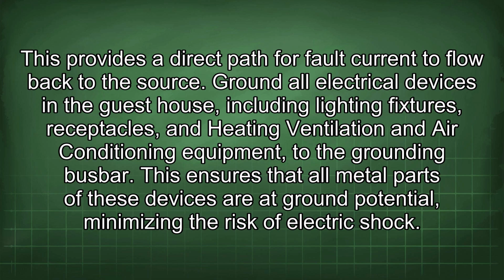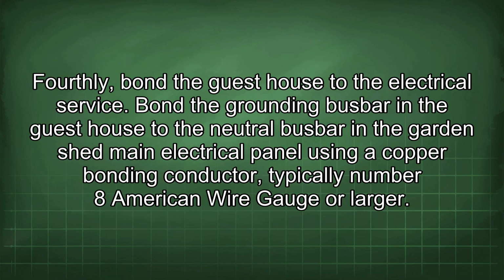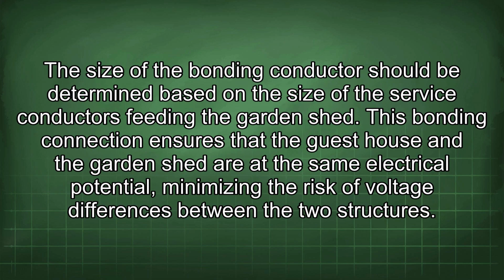Fourthly, bond the guest house to the electrical service. Bond the grounding busbar in the guest house to the neutral busbar in the garden shed main electrical panel using a copper bonding conductor, typically number 8 American wire gauge or larger. The size of the bonding conductor should be determined based on the size of the service conductors feeding the garden shed. This bonding connection ensures that the guest house and the garden shed are at the same electrical potential, minimizing the risk of voltage differences between the two structures.